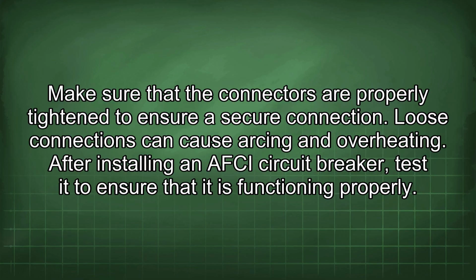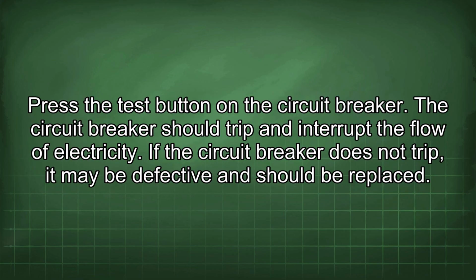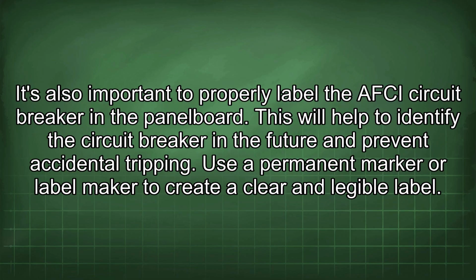After installing an AFCI circuit breaker, test it to ensure that it is functioning properly. Press the test button on the circuit breaker. The circuit breaker should trip and interrupt the flow of electricity. If the circuit breaker does not trip, it may be defective and should be replaced. It's also important to properly label the AFCI circuit breaker in the panel board. This will help to identify the circuit breaker in the future and prevent accidental tripping. Use a permanent marker or label maker to create a clear and legible label.